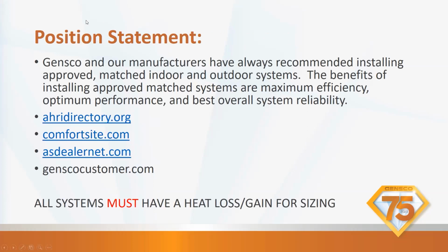Gensco and our manufacturers have always recommended approved matched indoor and outdoor systems. The benefits of installing approved match systems are maximum efficiency, optimum performance, and best overall system reliability. The other thing is that if you're trying to put a 410A system on an older coil or air handler, there's a potential there that indoor unit is going to blow up. And what I mean is blow the lines inside of the coil because they were never designed for the higher pressures of 410A. So we need to be careful for this stuff, okay?